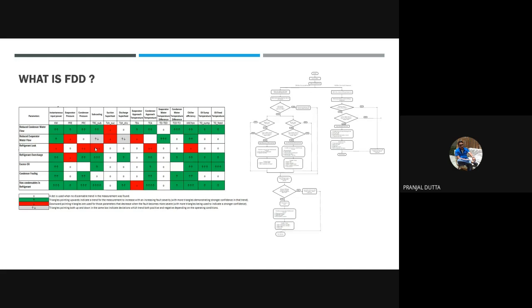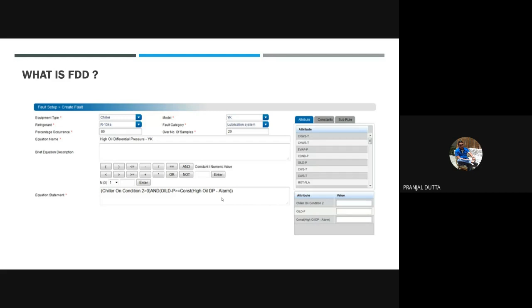After implementing all this logic, whenever there is an error, like refrigerant overflow, it will detect that and inform the energy manager, and accordingly it goes to the maintenance team, and they will take corrective actions on that particular issue. That is why it is called an enterprise management system. Rules are written this way. First condition: the chiller is on. Second: the oil pressure is higher than a set point, then there is an error on your oil pump.